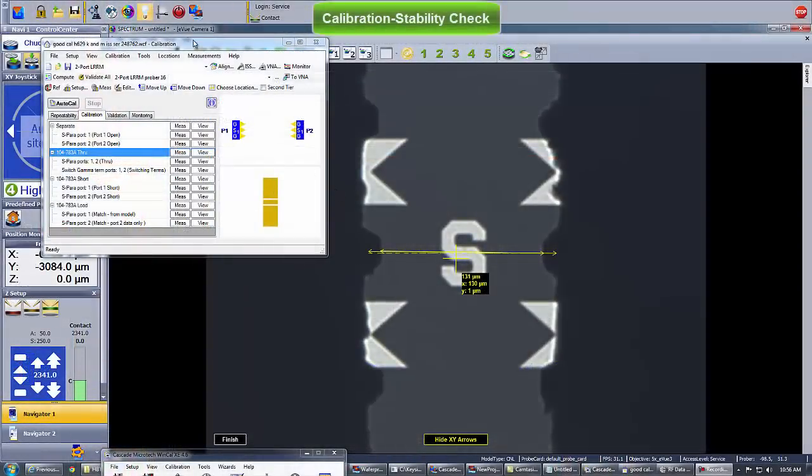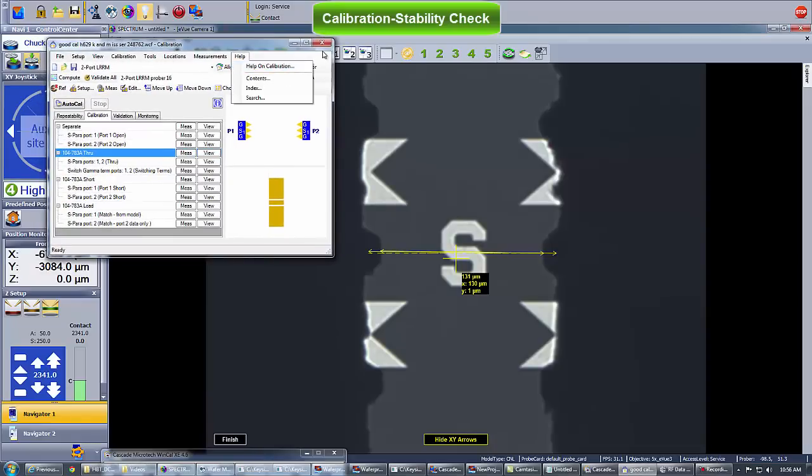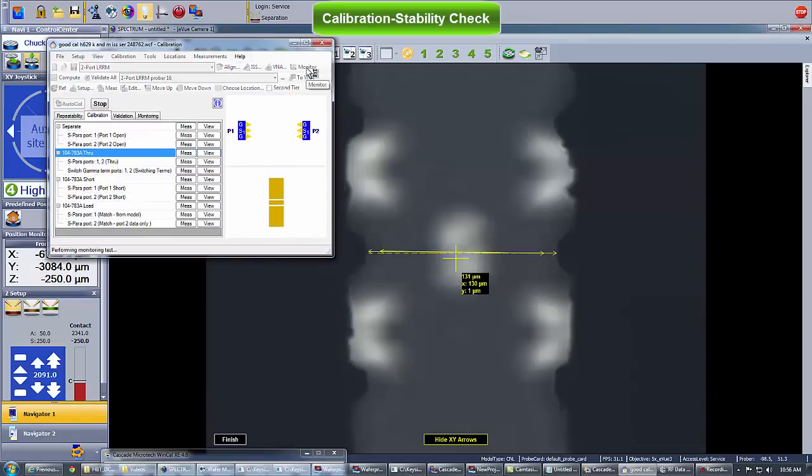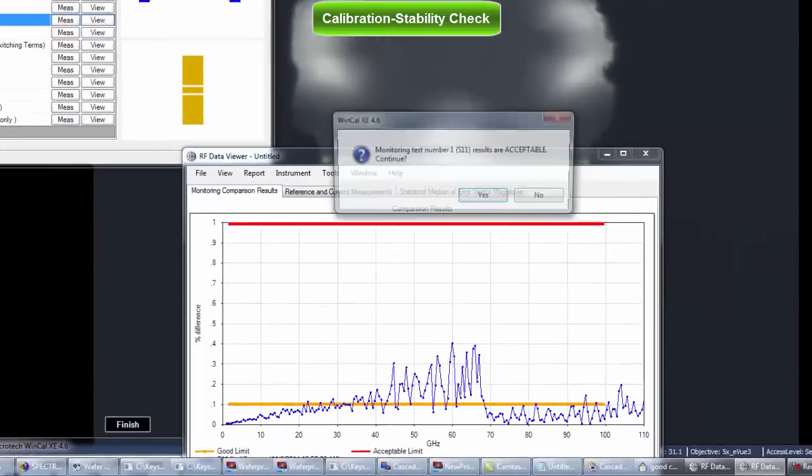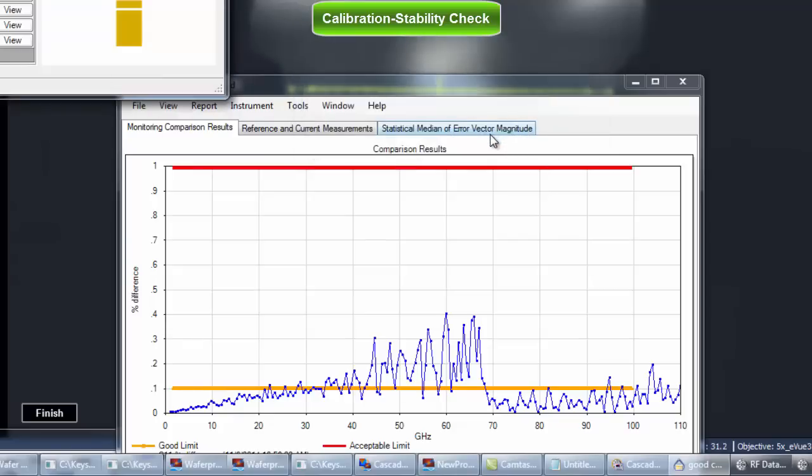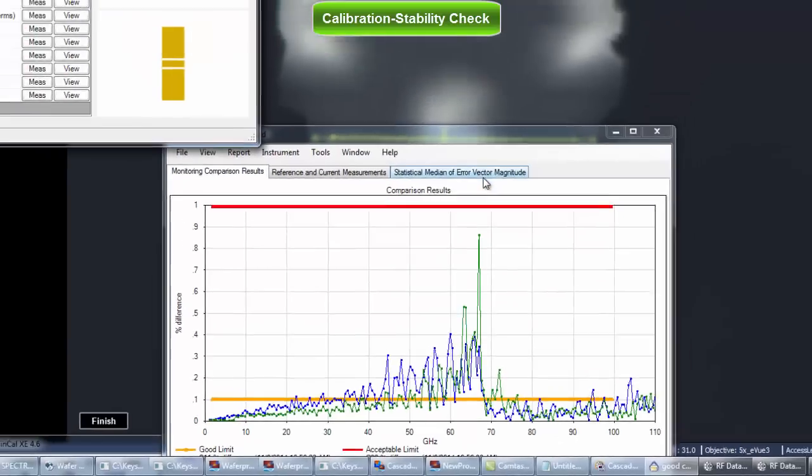WinCal can also check the calibration stability. This is typically done by comparing a new measurement of an open to the data measured during calibration. During a long test plan execution, WaferPro Express can periodically trigger the stability test to validate the calibration. This is very important to make sure measured data are still valid.